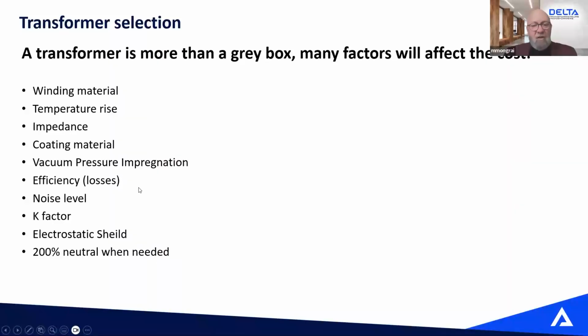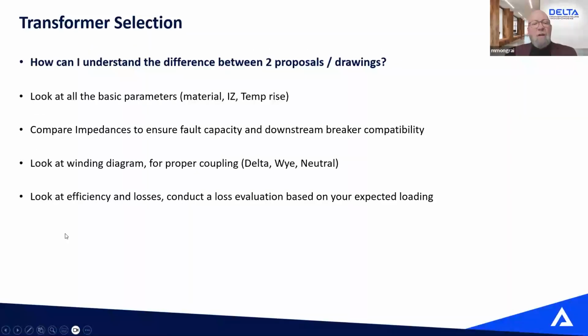Look at the efficiency, not just the fact that it's NRCan approved. What are the losses of the transformer, so you can figure out what's the efficiency of the transformer under full load condition? Do I need a transformer that is less noisy than a standard one? Do I need a K factor? Do I need a static shield? Do I need to oversize my neutral conductor? Because when you have harmonics, those harmonic currents come back by the neutral. So those are all questions you need to ask yourself.